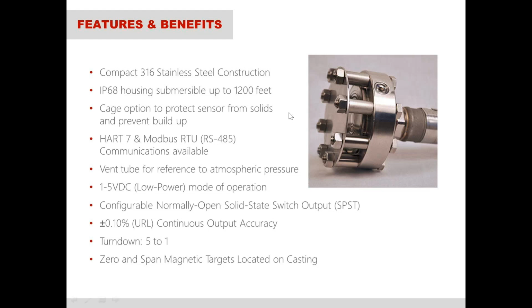Say if their tank is 4 foot or so. And of course you will get less accuracy. However, some people don't necessarily care if it's the difference between an accuracy of a 32nd of an inch to an accuracy of a half of an inch, and that might not be a big difference to them.